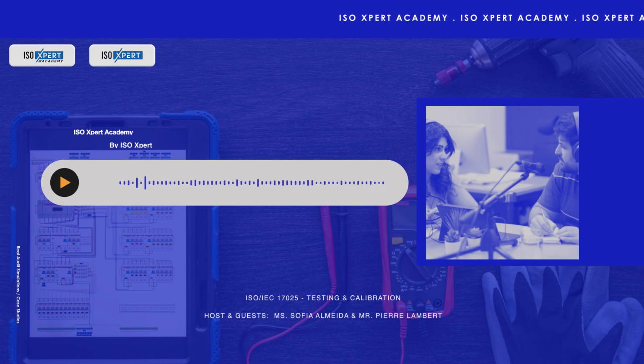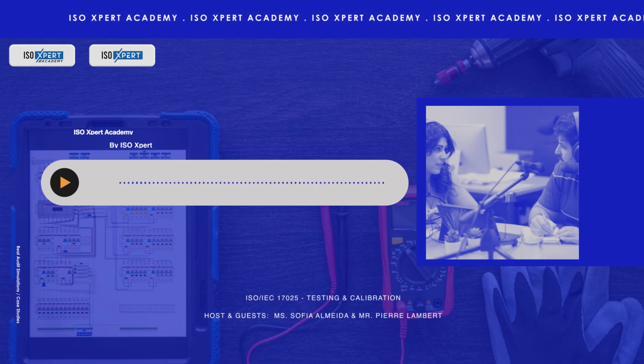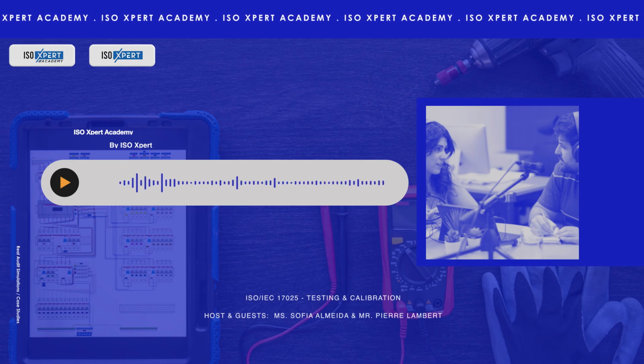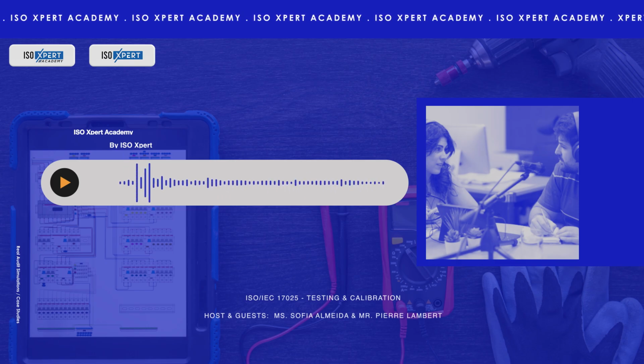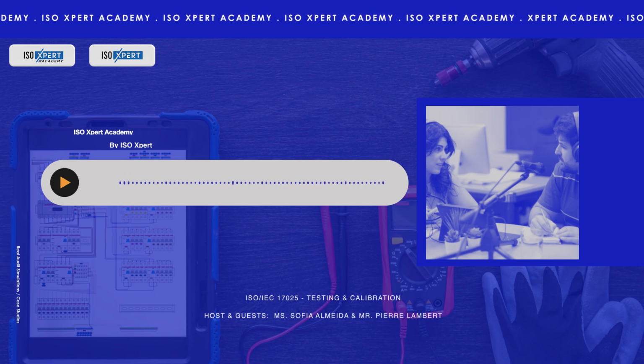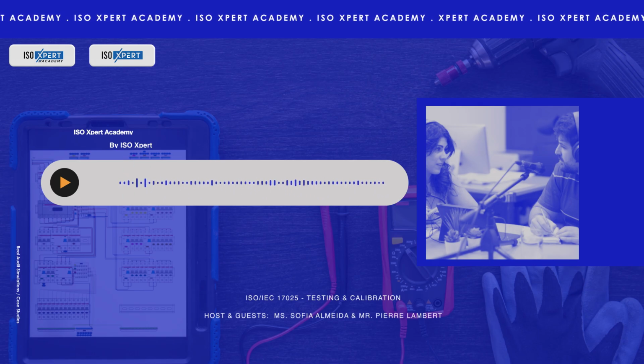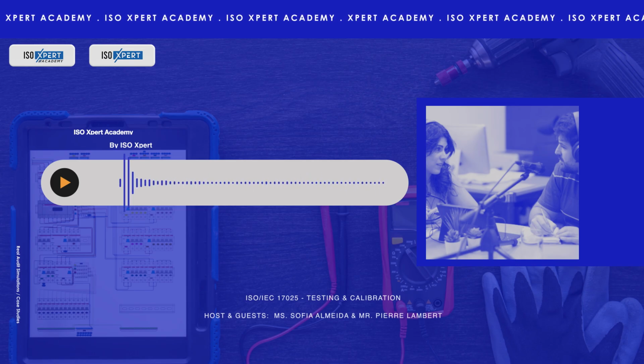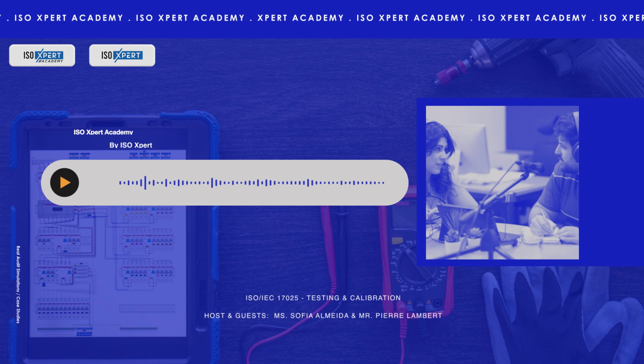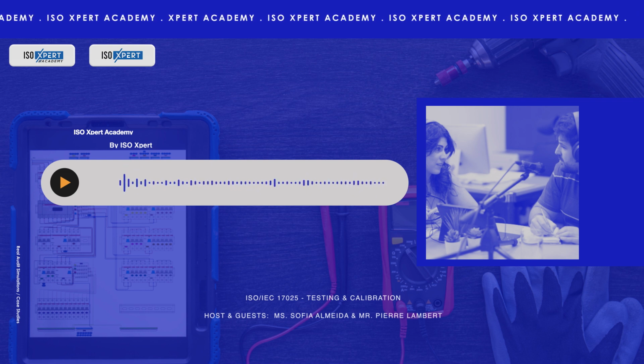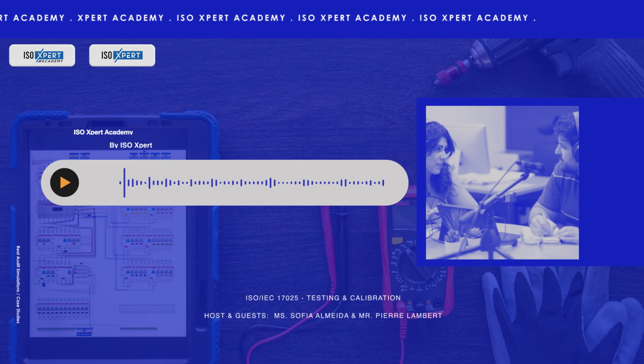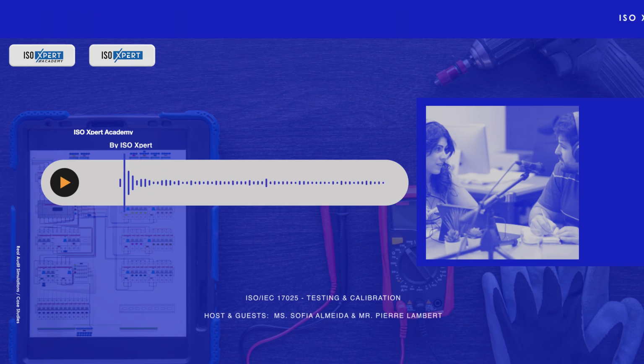And who is checking Perfect Calibration against this standard? The audit team was led by Asha Khan. Then there was Saeed Al-Mansouri as the technical auditor and Fatima Rahman observing the process. And it sounds like they didn't just look at one small corner of the lab. No, definitely not. It was comprehensive. The scope covered a whole range of their work: electrical calibration, temperature and pressure, dimensional metrology, that's measuring physical dimensions, and also mass and volume calibration. So tiny measurements up to big weights. Exactly. They were looking across the board. And their goals were clear, right? Check conformity, see if procedures were actually being followed. Yeah, evaluate technical competence, impartiality, which is key, and maybe most importantly, find areas where they could improve.